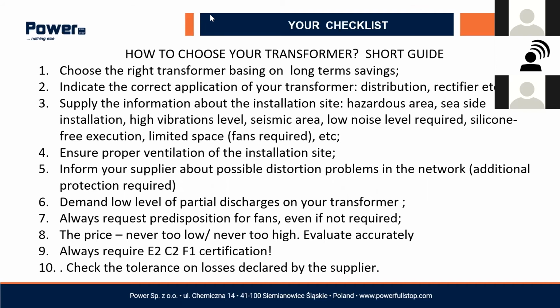And a very important point I'm always underlining many times is the partial discharges. The real quality of cast resin transformers is the partial discharges. According to the rule, the partial discharges must be lower than 10 picocoulomb. For some applications, especially if you are working with the German market, they also ask for 5 picocoulomb. I'm talking about partial discharges on the transformer, not on the windings. So this is also the point you should check. Sometimes somebody writes 10 picocoulomb on the winding. No, it must be on the transformer.